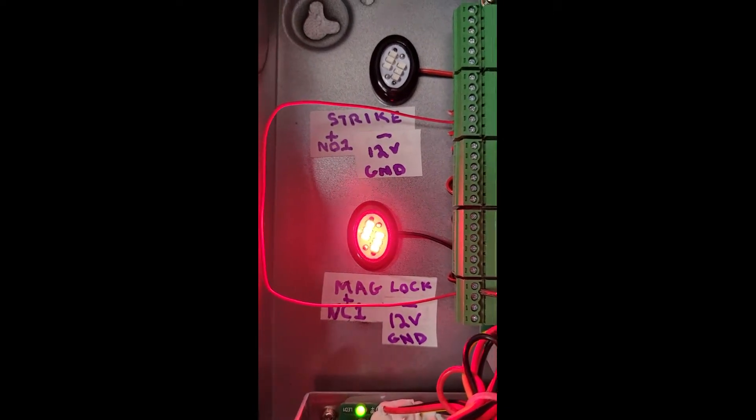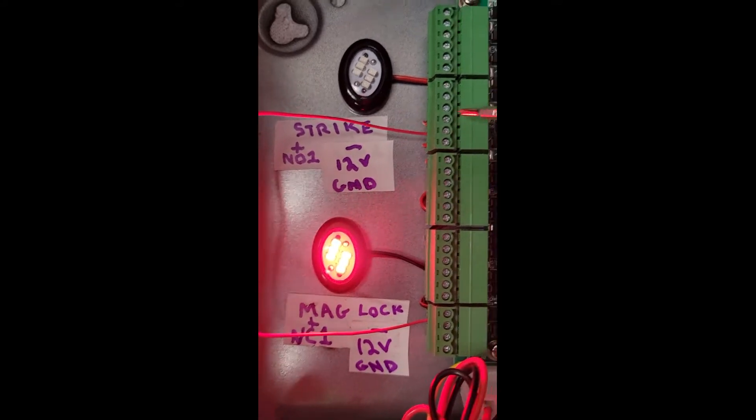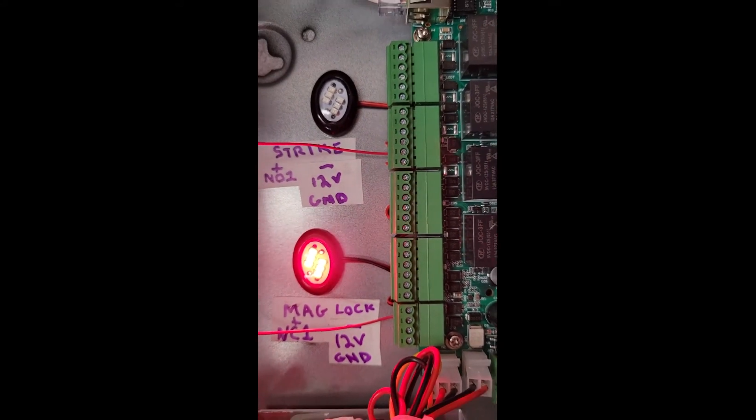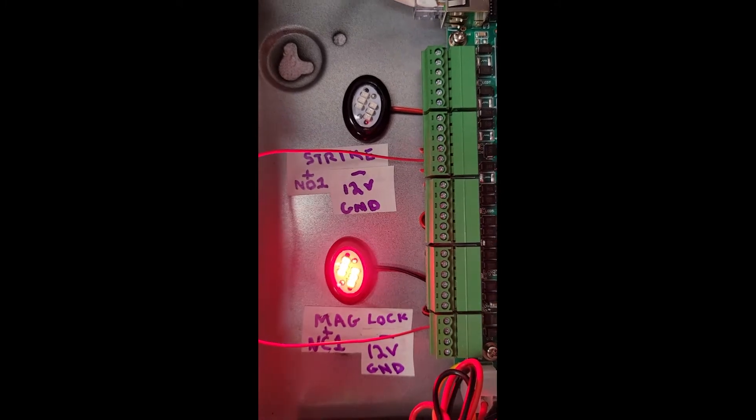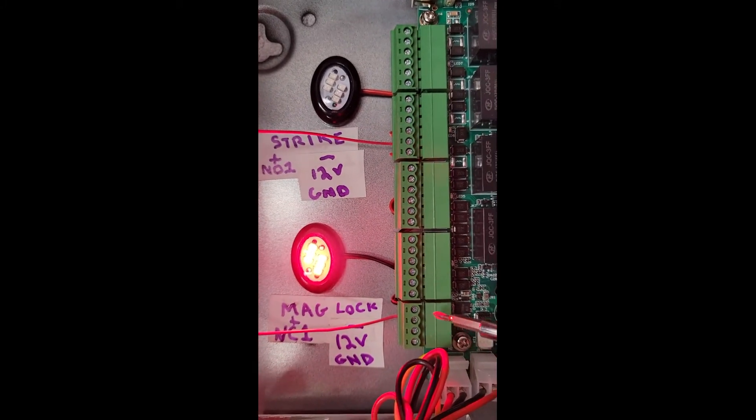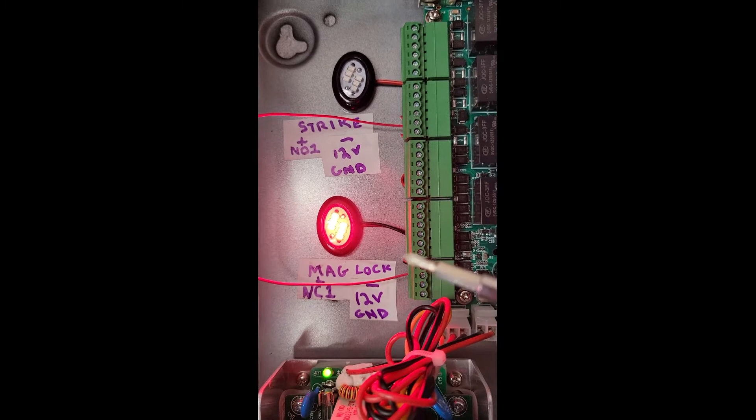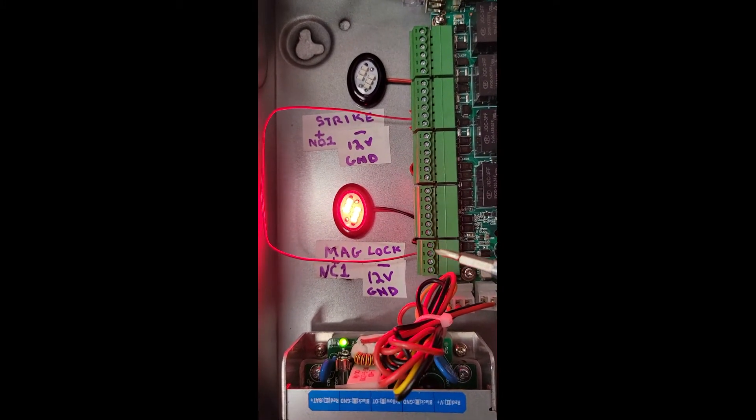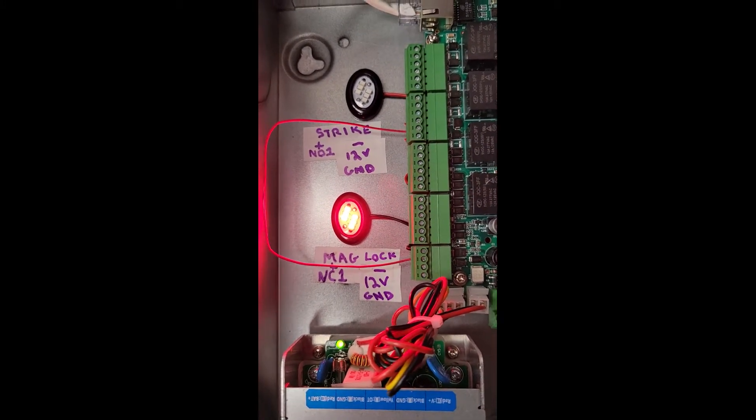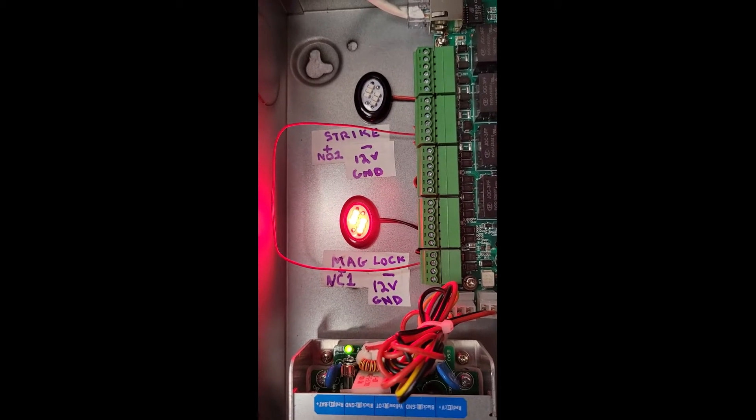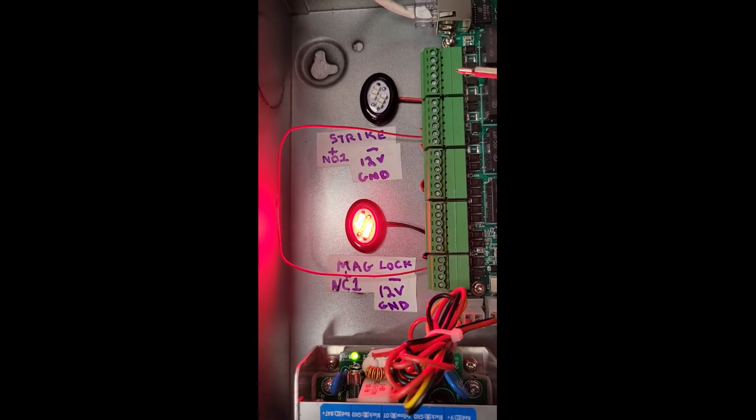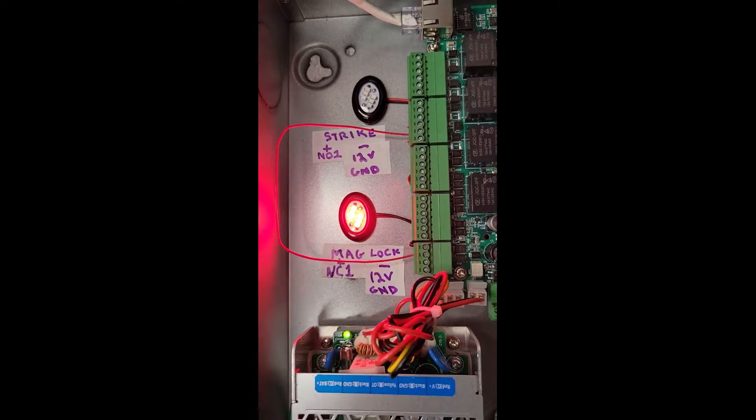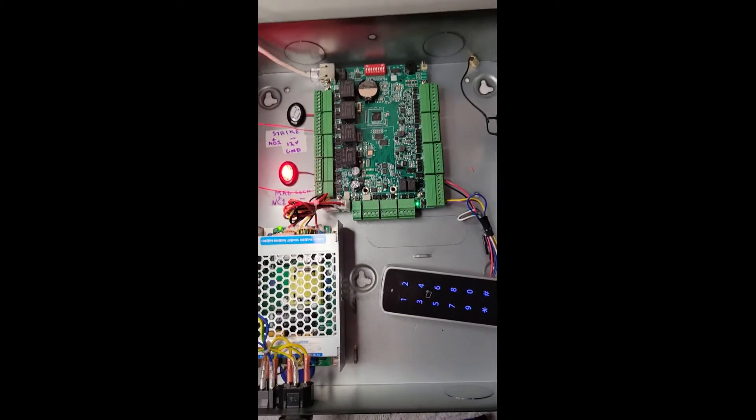If we had a door strike, that's going to go to normally open one, that's this third terminal here. And then we will have the negative side from the strike land on that 12 volt ground as well. So if we had a mag lock, we would have constant power. When a valid swipe occurs, that will drop and break power. If we had our door strike, it's not energized until we had a valid swipe. So that is the inside the panel look.